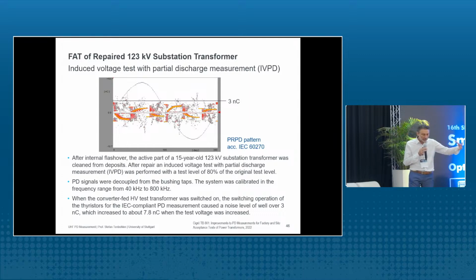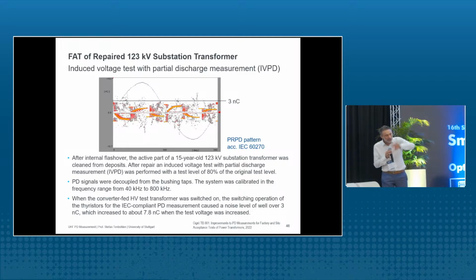So it was brought back to a repair factory, and they clean, you know, after such a failure, you have carbon deposits on the winding, and you have to clean it. But this repair factory didn't have a vapor phase oven, so they could clean the windings just by spraying oil on the winding and washing it, like you wash a car, more or less. Yeah, you do not use water, but you use oil to remove the carbon particles. But of course, you have also carbon particles inside the winding, which are difficult to remove.